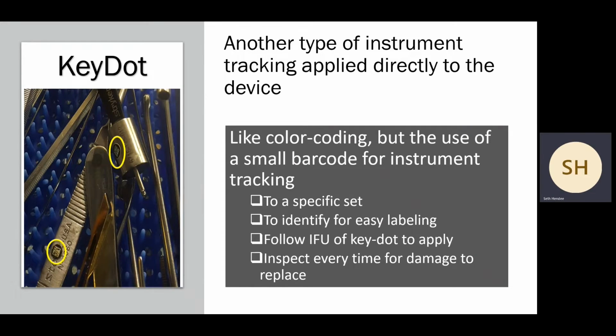What about those little 3D barcodes, the key dot or info dot? Another type of instrument tracking that's applied directly to a device, gets down to the device level tracking. It's like color coding, but it uses a small barcode. It links things to specific sets, easy to identify individual instruments for labeling. You still have to follow the IFU for the way it's applied, and it has to be inspected every time. If they begin to flake, chip, or pick up debris, you cannot use those either.